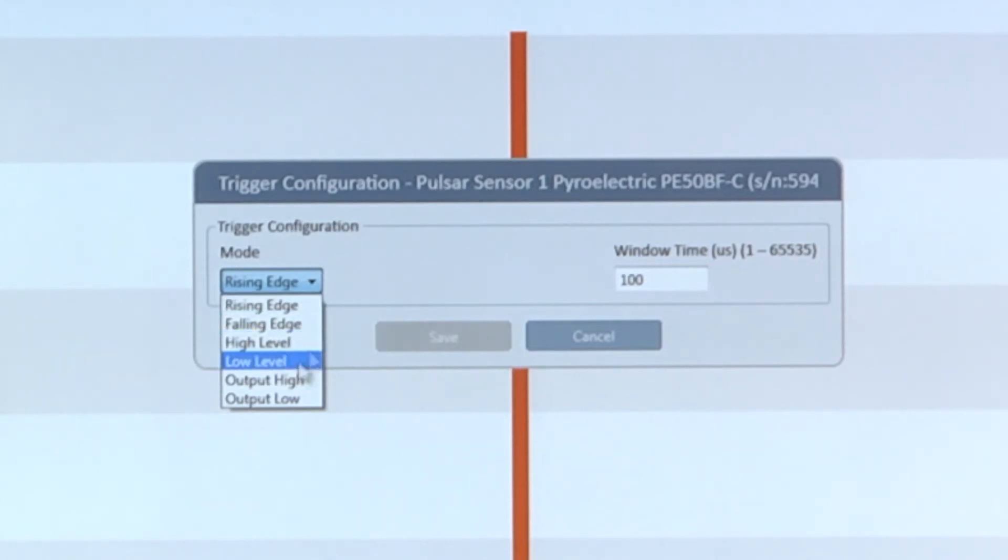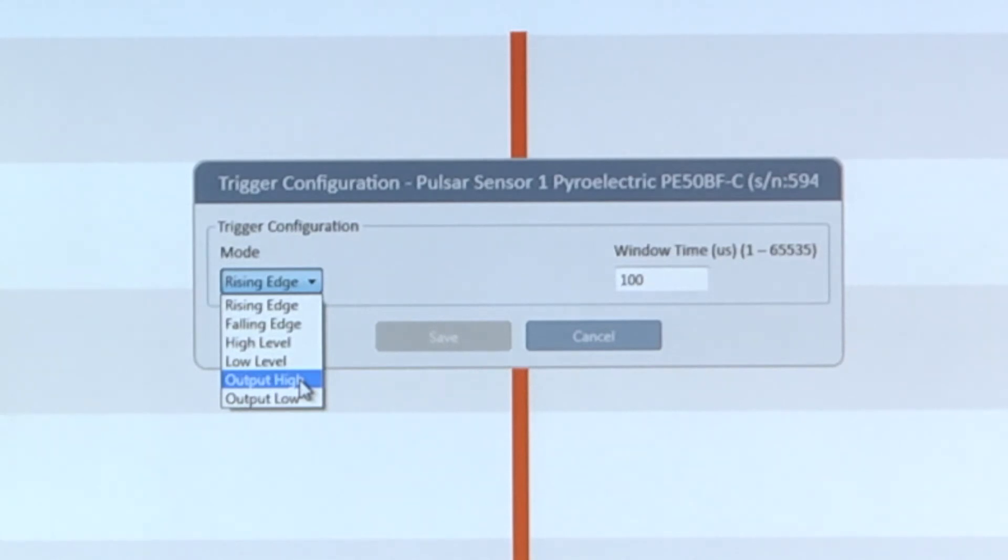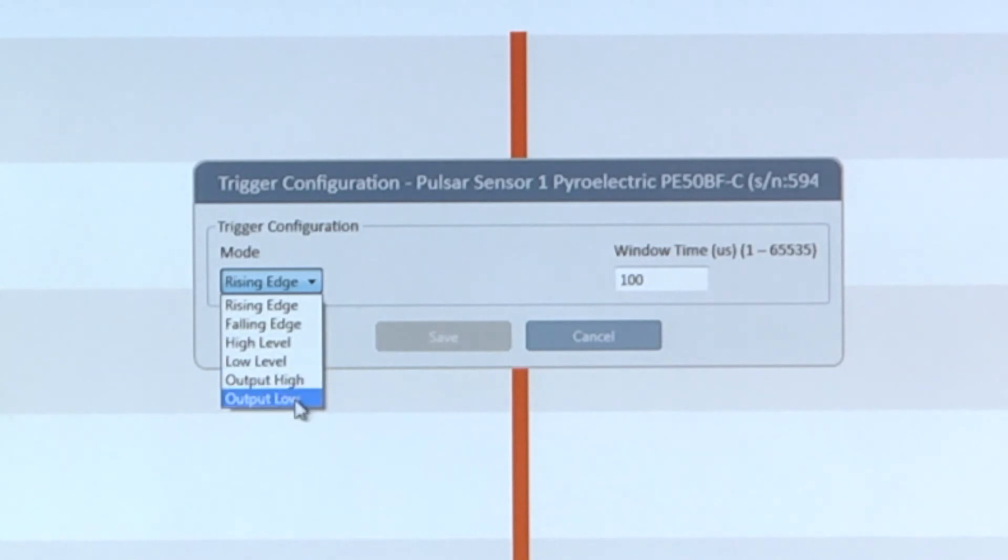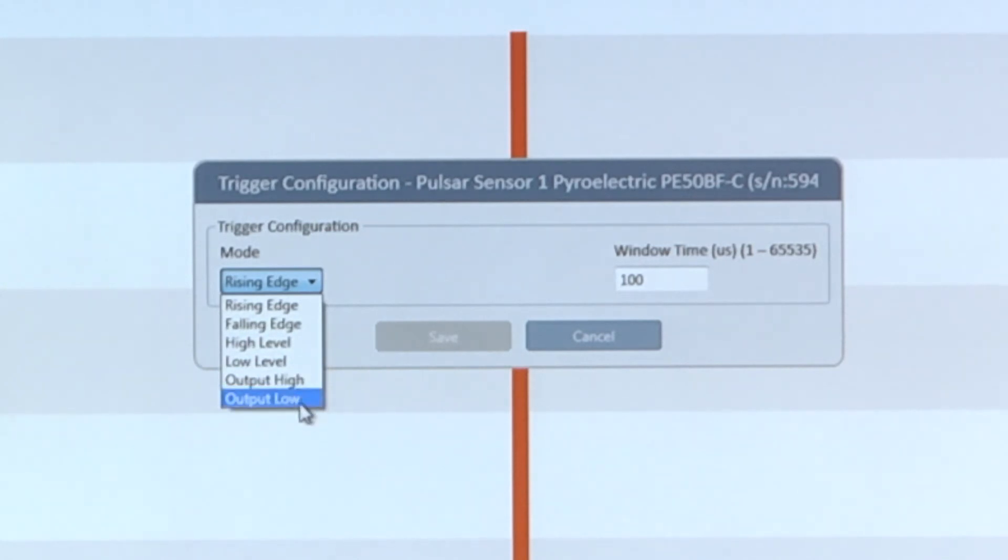We're also able to configure StarLab to send out a pulse from that BNC connector any time a laser pulse is detected. This can be used, for example, to trigger some external circuit. Here we would configure StarLab to send out a pulse that's either high or low by selecting output high, output low from the trigger configuration mode.